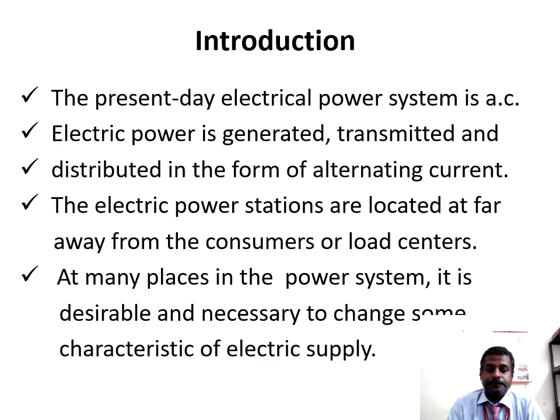So now I will tell the definition for the substation. It is an assembly of apparatus, that means a set of equipment installed to perform voltage transformation, voltage reduction or voltage increase, switching on and off, power factor correction. Okay, so power factor can be improved from 0.8 to 0.9 or unity, power and frequency converting operations. So these operations are performed in a particular place. That is the definition for the substation: assembly of apparatus installed to perform voltage transformation, switching, power factor correction, power and frequency converting operations.